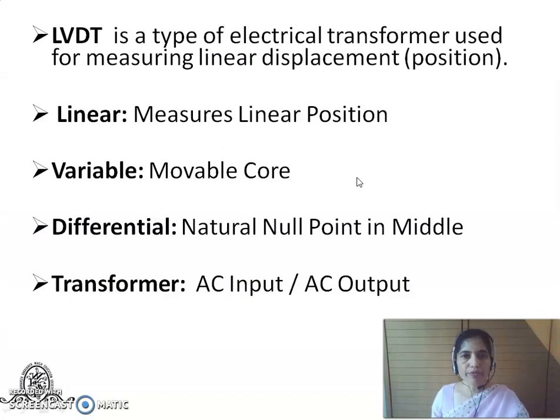Thus, LVDT is a type of electrical transformer which is used for measuring linear displacement. The reason why the word linear is included is because this transducer measures linear position. The core is moving along a line in the cylindrical pipe. Therefore, it is linear displacement measurement. Variable, because the core is moving, it is varying its position for measurement. Differential, because the natural null point is in the middle, but as the core moves away towards one of the secondaries, the output voltage is a difference between the two induced voltages, therefore differential. And finally, the word transformer, because the input given to the primary is AC, alternating current, and the output which is derived from the two secondaries is again AC output. Therefore, it is a transformer.